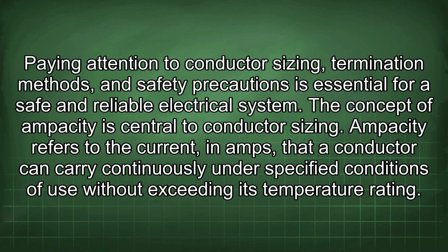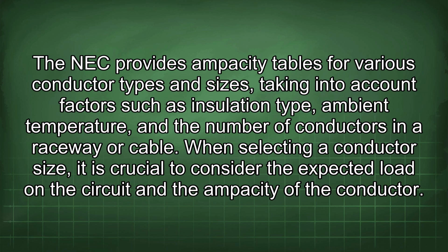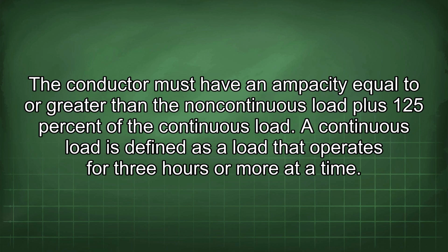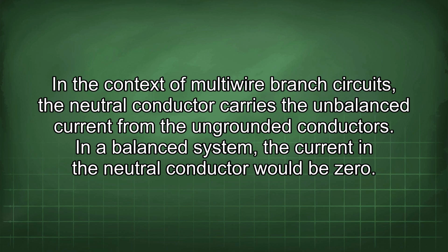Ampacity refers to the current, in amps, that a conductor can carry continuously under specified conditions of use without exceeding its temperature rating. The NEC provides ampacity tables for various conductor types and sizes, taking into account factors such as insulation type, ambient temperature, and the number of conductors in a raceway or cable. When selecting a conductor size, it is crucial to consider the expected load on the circuit and the ampacity of the conductor. The conductor must have an ampacity equal to or greater than the non-continuous load plus 125% of the continuous load. A continuous load is defined as a load that operates for 3 hours or more at a time. In the context of multi-wire branch circuits, the neutral conductor carries the unbalanced current from the ungrounded conductors.